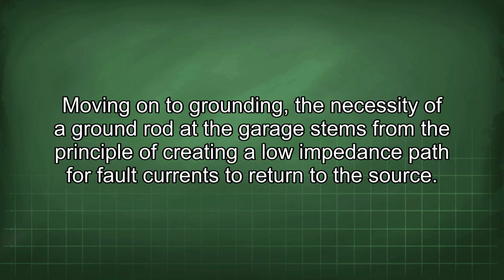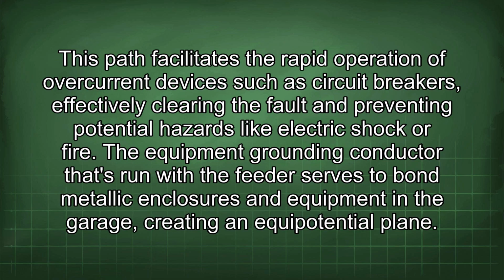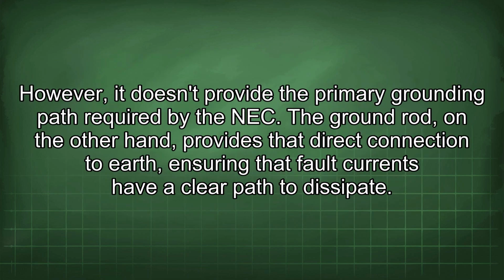Moving on to grounding, the necessity of a ground rod at the garage stems from the principle of creating a low impedance path for fault currents to return to the source. This path facilitates the rapid operation of overcurrent devices such as circuit breakers, effectively clearing the fault and preventing potential hazards like electric shock or fire. The equipment grounding conductor that's run with the feeder serves to bond metallic enclosures and equipment in the garage, creating an equipotential plane. However, it doesn't provide the primary grounding path required by the NEC.